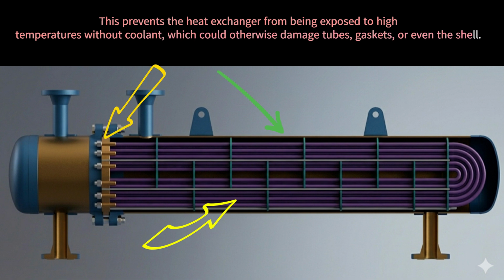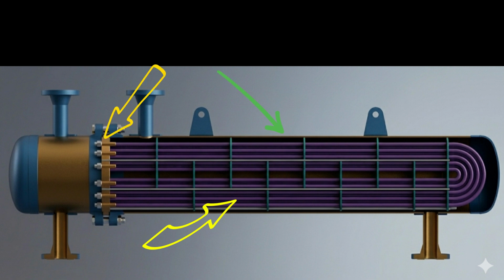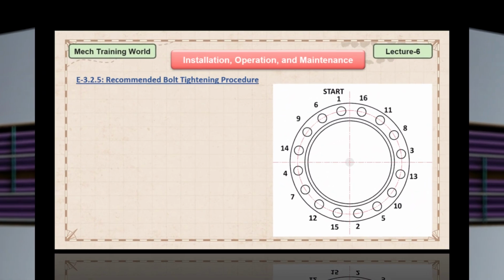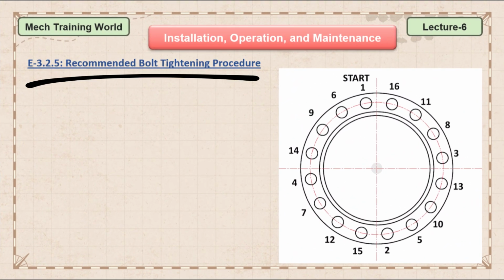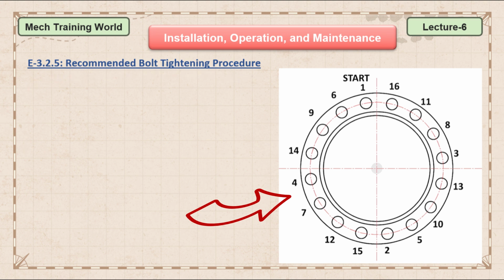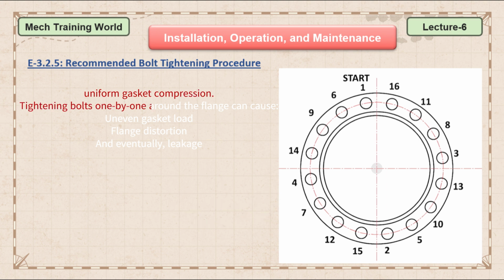Now let's move to another topic, the bolt tightening procedure, which is often underestimated. Look at this bolt tightening pattern. You'll notice it's not sequential or circular. The critical idea here is uniform gasket compression. Tightening bolts one by one around the flange can cause uneven gasket load, flange distortion, and eventually leakage.